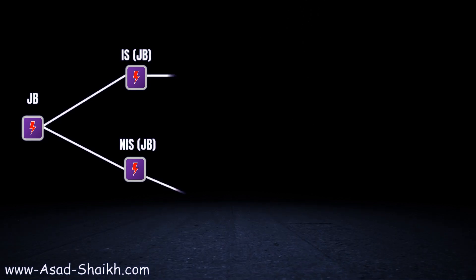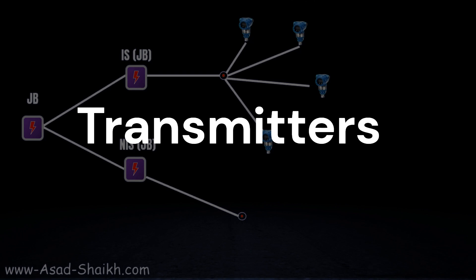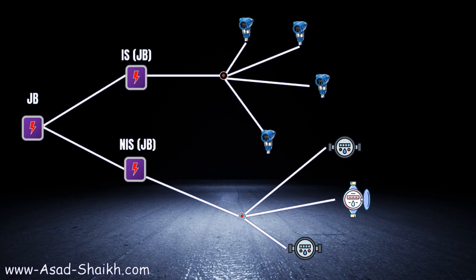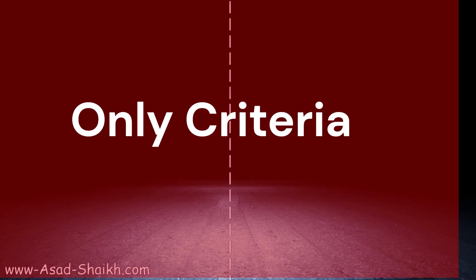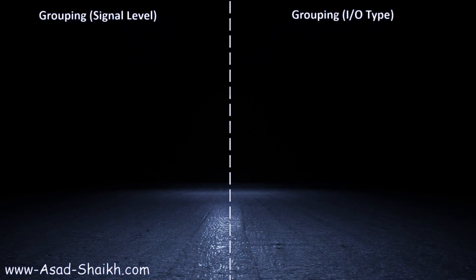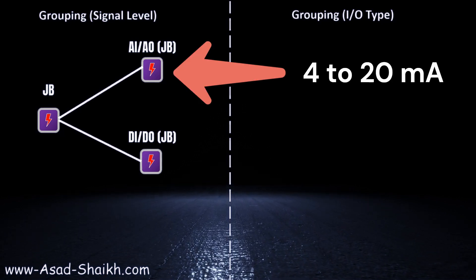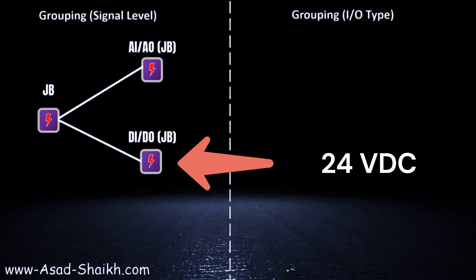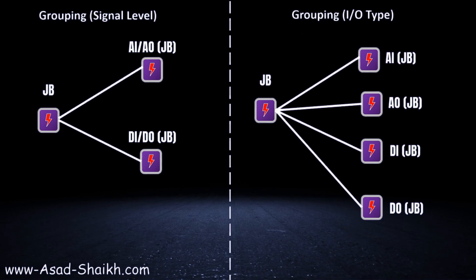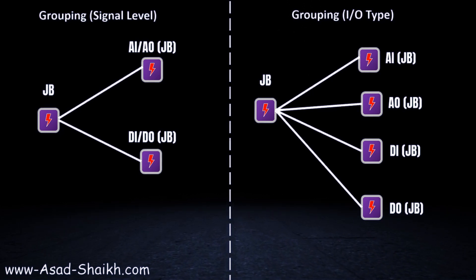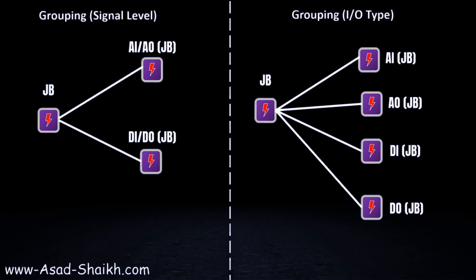An IS JB is where IS devices such as transmitters are connected, and an NIS JB is where devices like solenoid valves and magnetic flow meters, which require higher power, are allocated. Beyond that, certain clients require further segregation by signal level — for example, AI and AO (4–20 mA signals) in one JB, and DI/DO in another. Some clients, such as on Saudi Aramco projects, require AI, AO, DI, and DO junction boxes separately. Generally though, IS and NIS JBs are the most cost-effective choice.